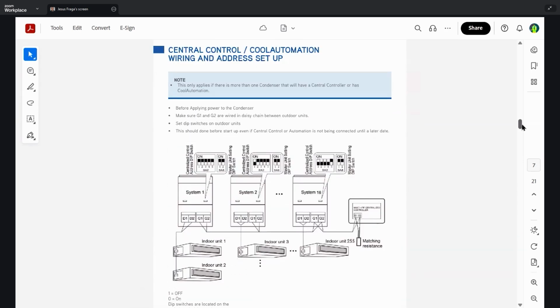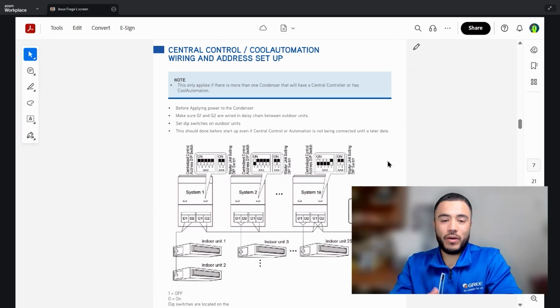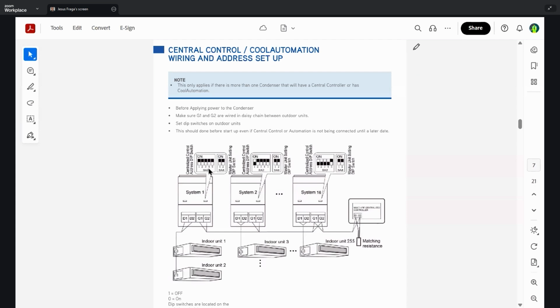So moving on to central control and CoolAutomation, wiring and address setup. As I stated earlier on the previous slides, a lot of this information stays the same, so the same applies here. The note here is this only applies if there's more than one condenser that will have a central controller or CoolAutomation. So if we have, for instance, 16 systems in line here, addressing strategy is pretty simple. As we see here, we know that this is always going to be the first system, because all the dip switches are in the off position. And once we go to the next system, we flip the first, we flip the second, and so forth. And we'll see that in the chart on the next page for you guys.